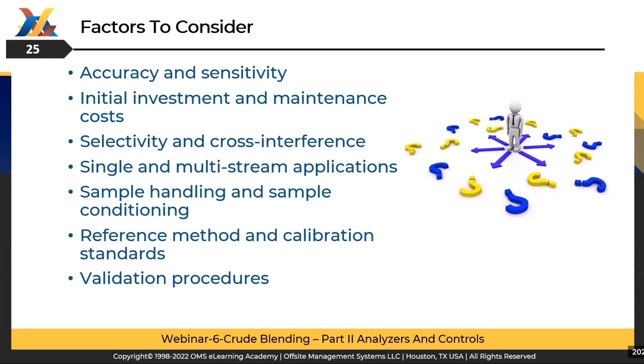Next slide, please. Critical success factors. At the earliest system design stage, the process stream must be defined by operating conditions and complete sample composition. Then a roadmap for process analyzer implementation should be established by considering the following critical factors. First of all, the defined measurement technique to be used, and availability of the same method used in the laboratory or some other. We always prefer to use the same method used in the laboratory, but in many cases, especially with crude oil, it's not applicable.